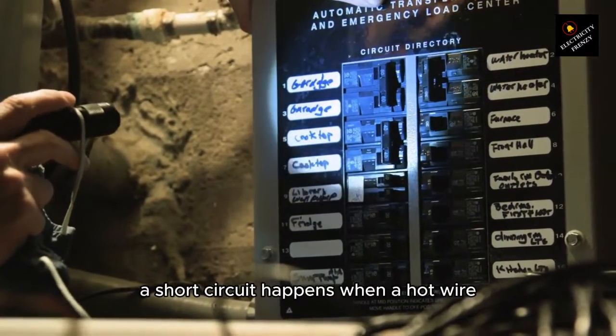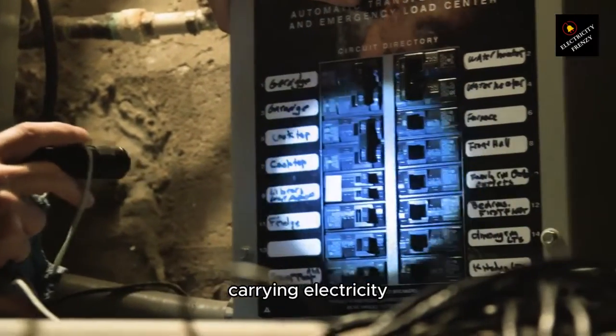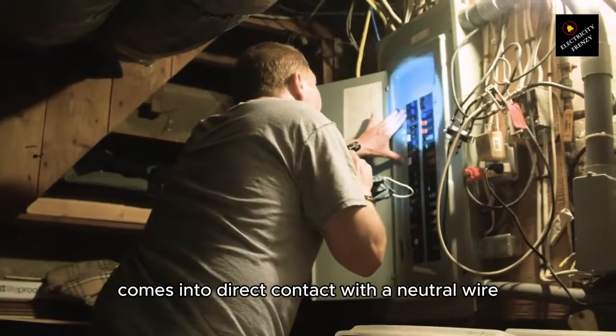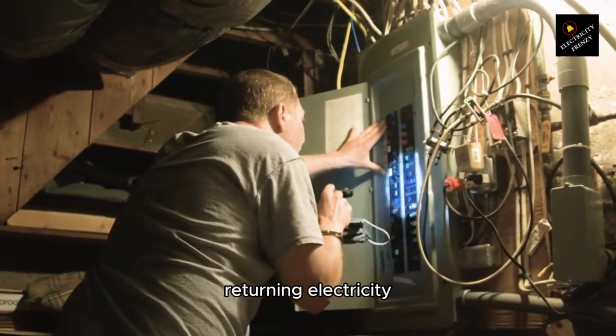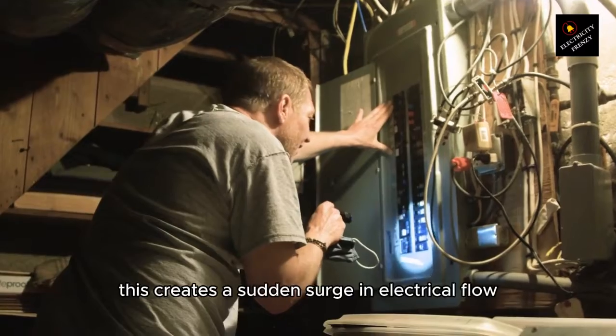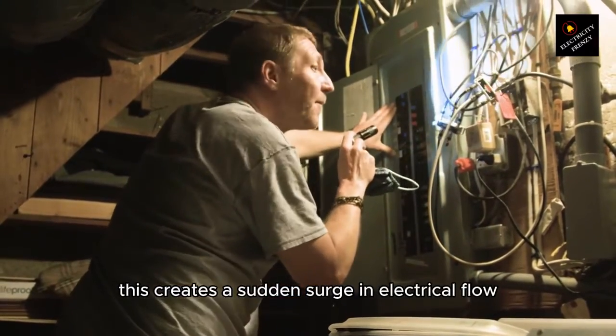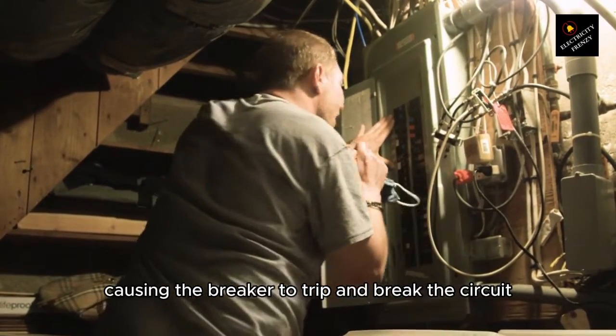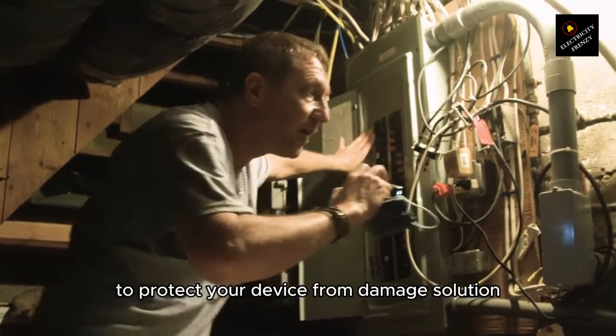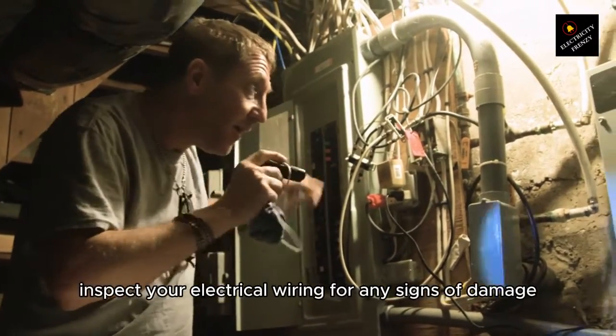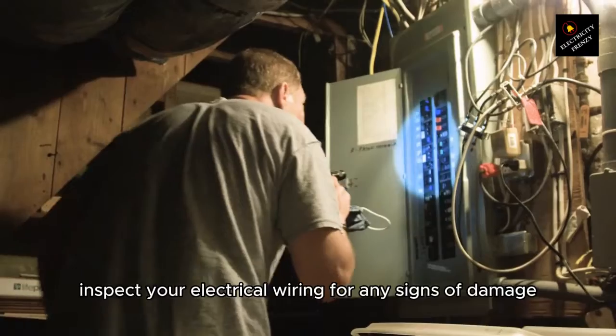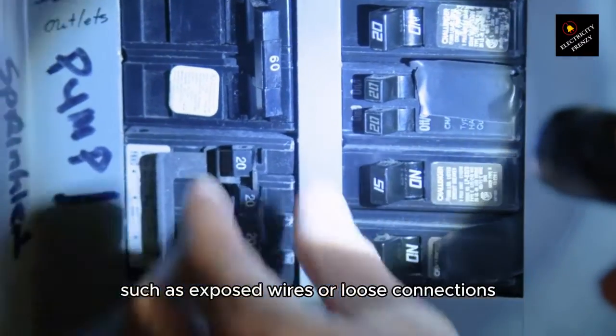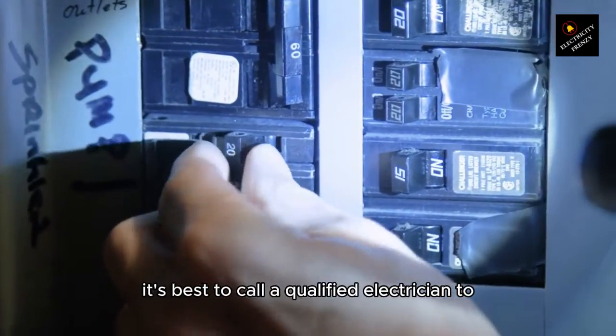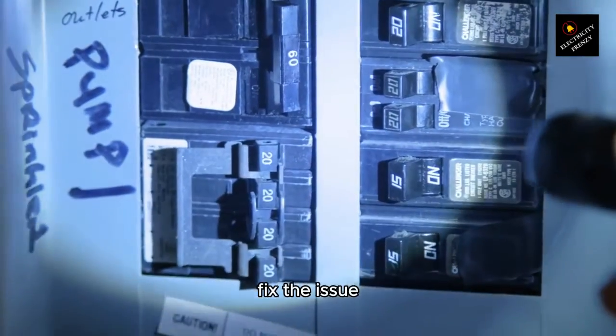Short circuit. A short circuit happens when a hot wire, carrying electricity, comes into direct contact with a neutral wire, returning electricity, or a ground wire. This creates a sudden surge in electrical flow, causing the breaker to trip and break the circuit to protect your device from damage. Solution: inspect your electrical wiring for any signs of damage, such as exposed wires or loose connections. If you find any, it's best to call a qualified electrician to fix the issue.